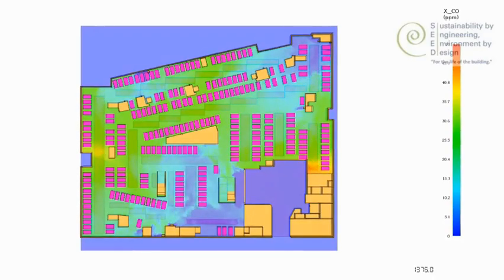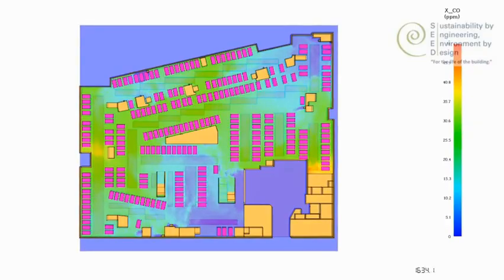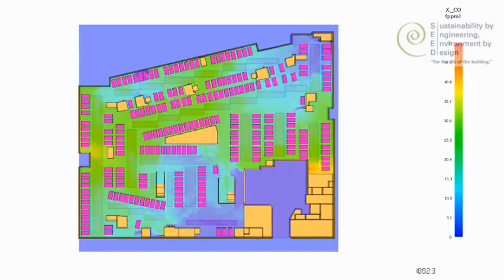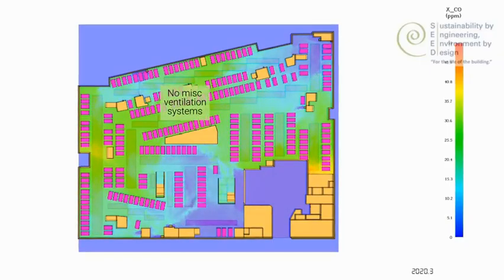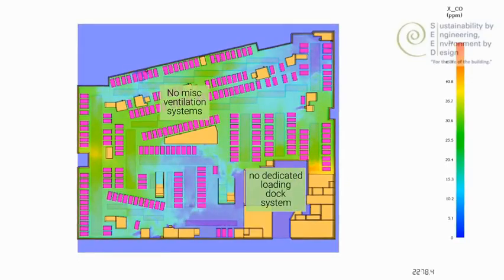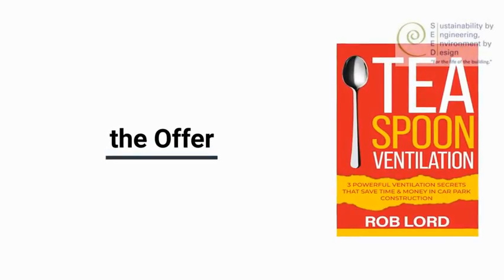We want to demonstrate this to you. We often use CFD modelling to demonstrate this, and in this example we've got a large loading dock used in the worst-case hour as a source of fresh air, and that fresh air bleeds in and dilutes large parts of the car park. We don't need a dedicated loading dock system, and we don't need dedicated miscellaneous ventilation systems.